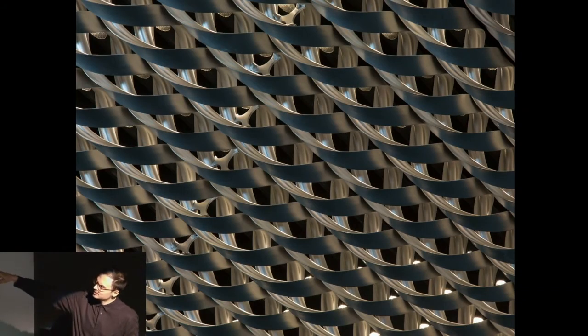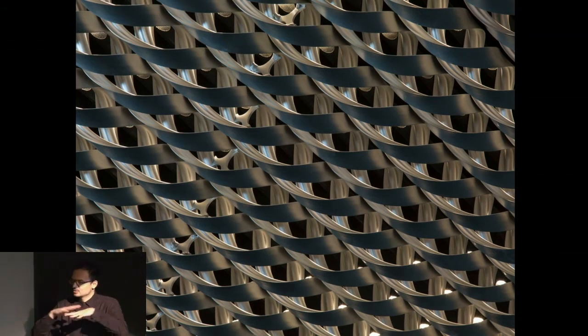Copper pipes are integrated into the spirals, which here are extruded aluminium, twisted and spiraled. Normally radiant ceilings are a flat surface, and that surface area of exchange is limited. By spiraling it here, we increase the effective surface area by threefold. So it means we can get the same amount of cooling, but with tepid water instead of cold water, because the equation for cooling is proportional to the temperature difference and the surface area.